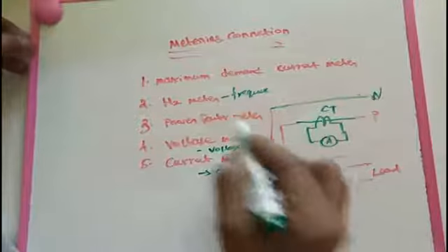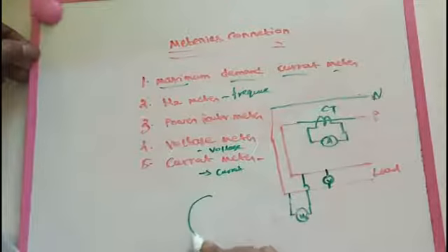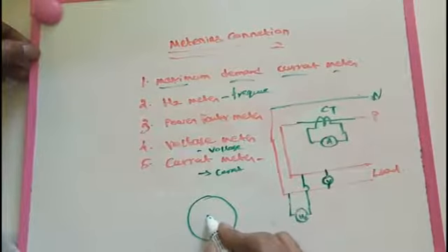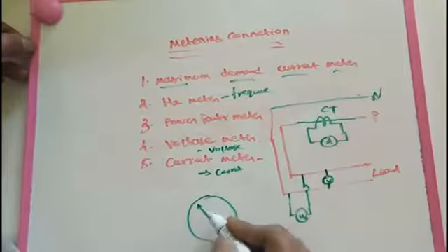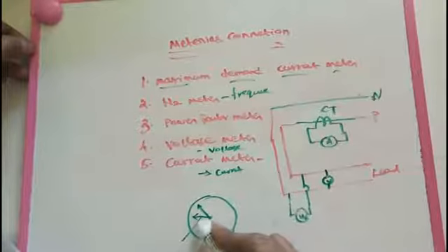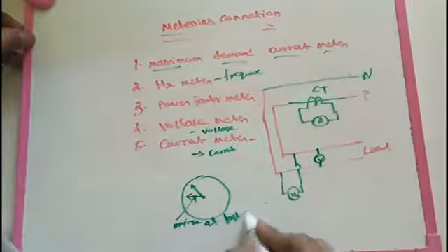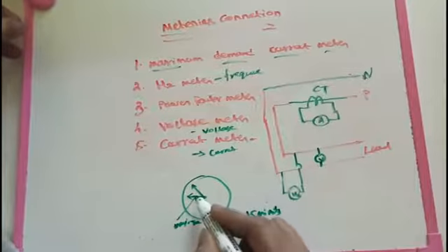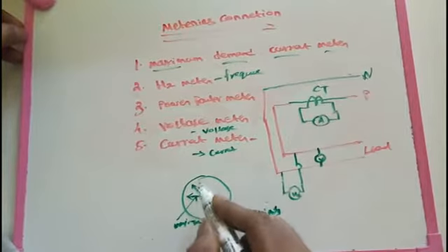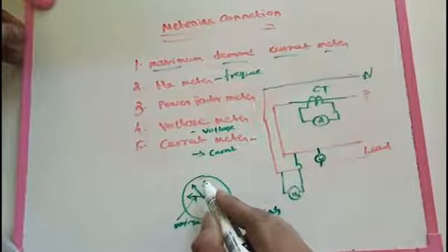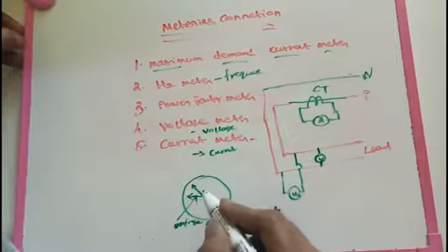After those three meters, we see the maximum demand indication current meter. It has two needles. One needle indicates the current flowing at that instant, and the other needle indicates the maximum demand reached in the last 15 minutes. For example, if 400 amperes flowed 10 minutes ago, that is recorded and the needle stays at that position. That is the purpose of the maximum demand indication meter.